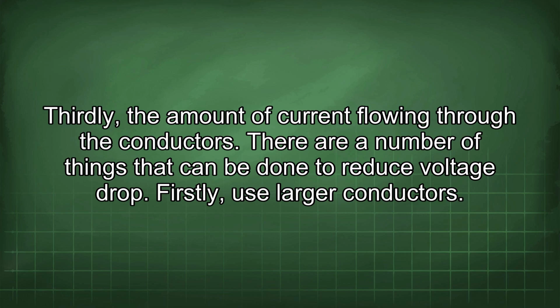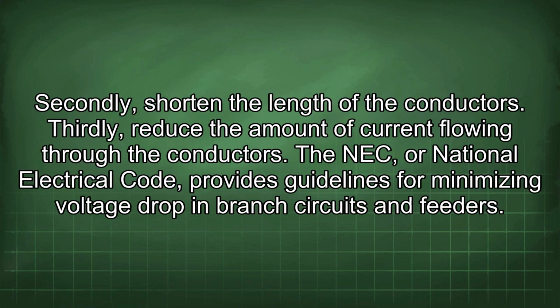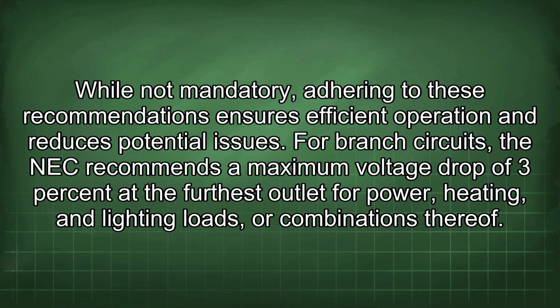There are a number of things that can be done to reduce voltage drop. Firstly, use larger conductors. Secondly, shorten the length of the conductors. Thirdly, reduce the amount of current flowing through the conductors. The NEC, or National Electrical Code, provides guidelines for minimizing voltage drop in branch circuits and feeders. While not mandatory, adhering to these recommendations ensures efficient operation and reduces potential issues.